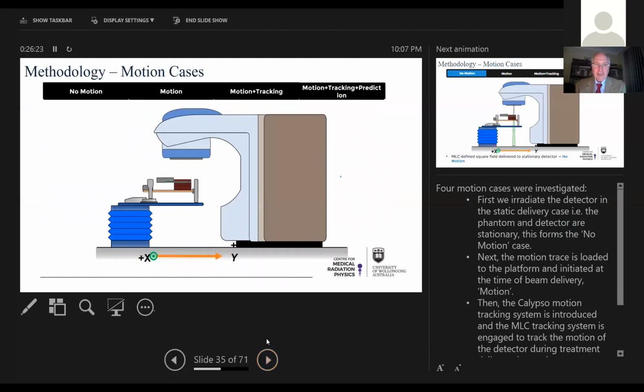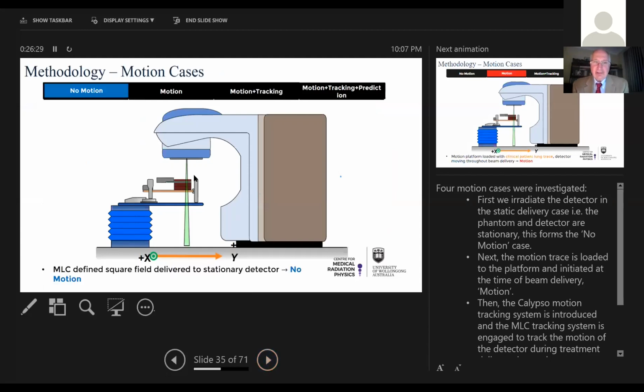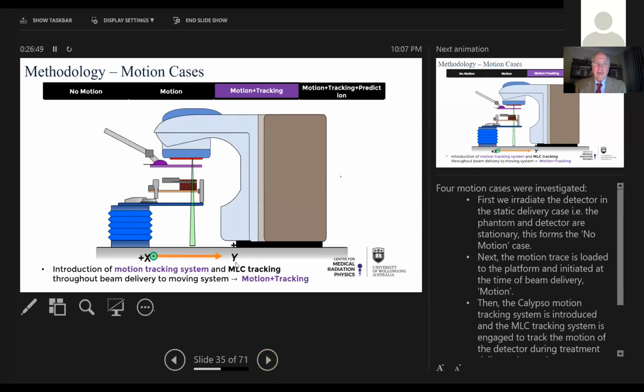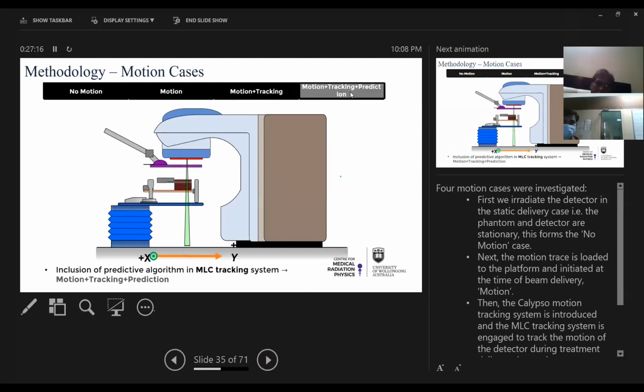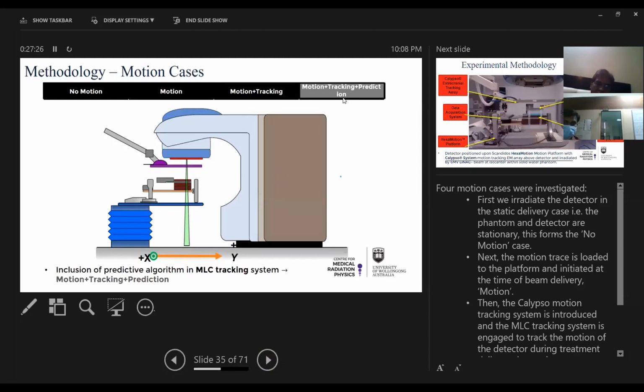I just would like to explain what we're doing here. First of all, static radiation, no problem. The tumor is stationary, you can deliver dose quite accurately. However, if you're not doing motion tracking and the tumor is moving, you're getting blurring of dose, and unfortunately, the margin should be very large. When you're doing tracking and motion, you're doing much more accurate, but even here a problem exists because unfortunately, the multi-leaf collimator is a mechanical system, and the tumor has quite high acceleration at the end when the tumor starts to move back, and a mechanical system can't afford such acceleration. So you need to have so-named motion tracking prediction. So you need to learn how the tumor is moving for the first 30 seconds, and then use an algorithm which predicts the position of the tumor.